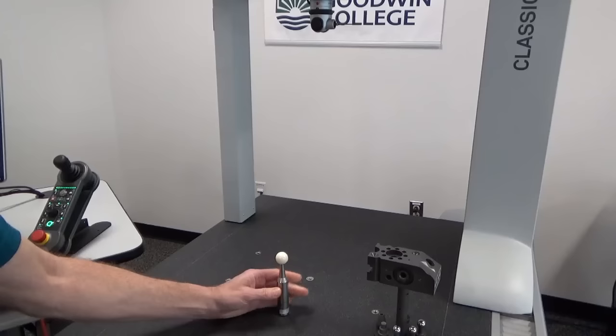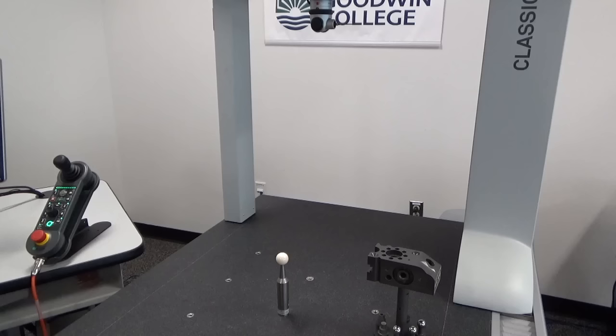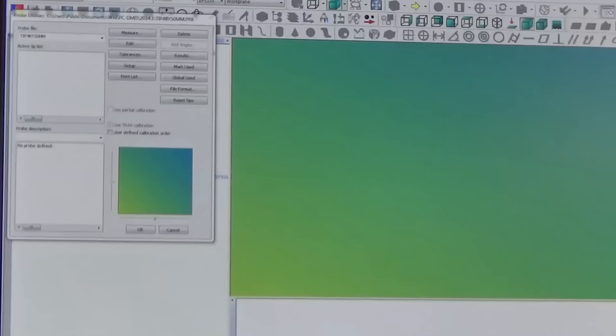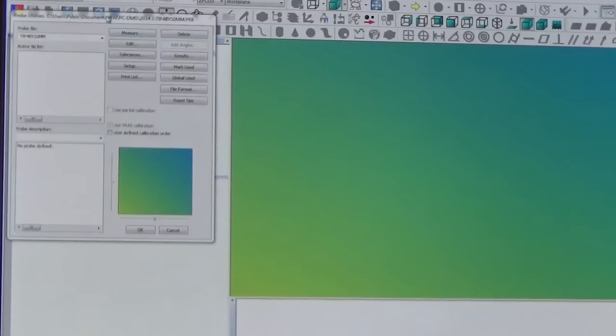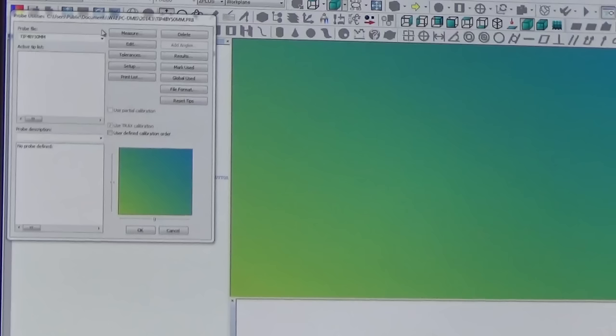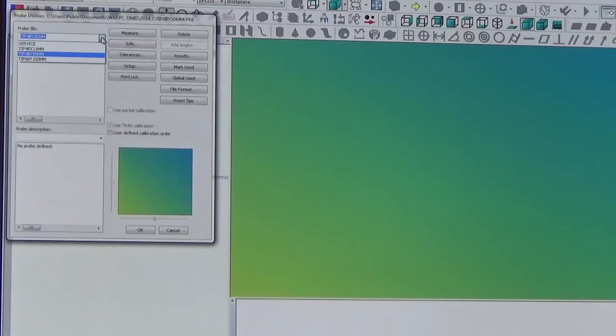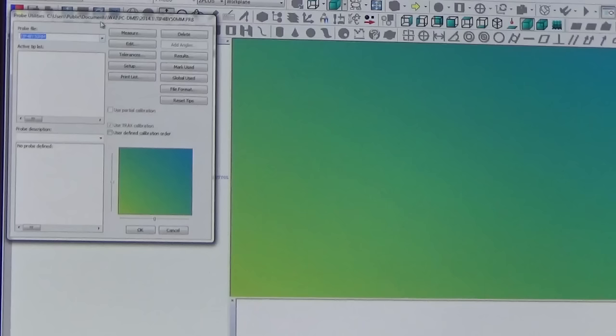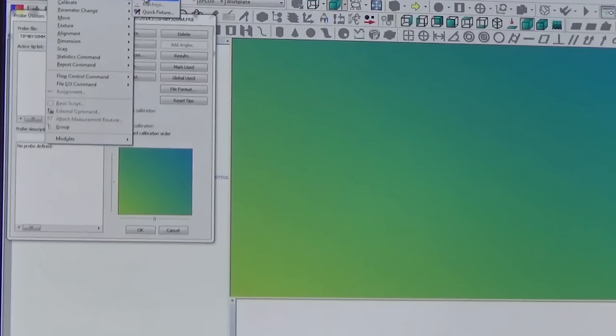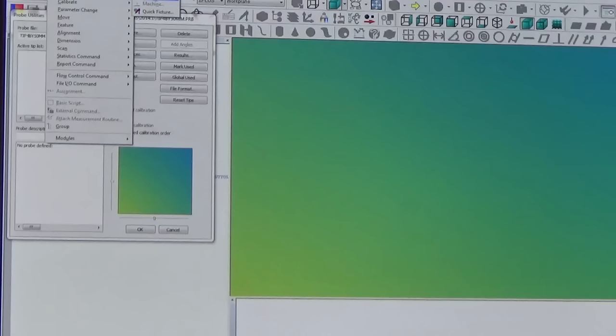So from here we're going to go take a look at the software, we have a number of things we need to set up in it. So when we go into the software and we open up a new file, we're going to write a brand new program, you're going to get this probe utilities dialog box straight up. In it you can define which probe you're going to use and their calibration files are attached.